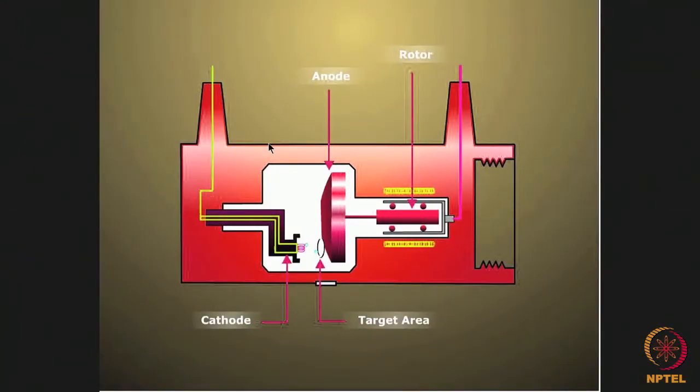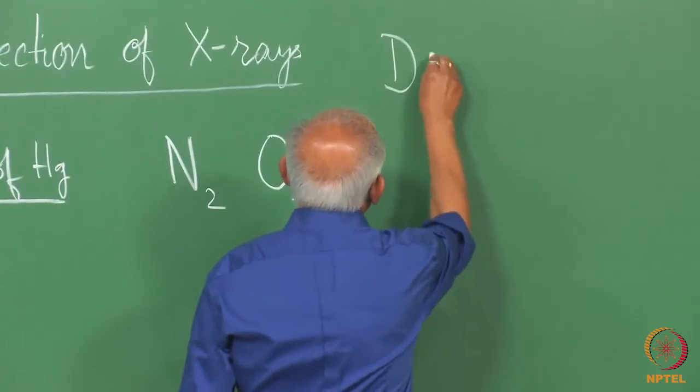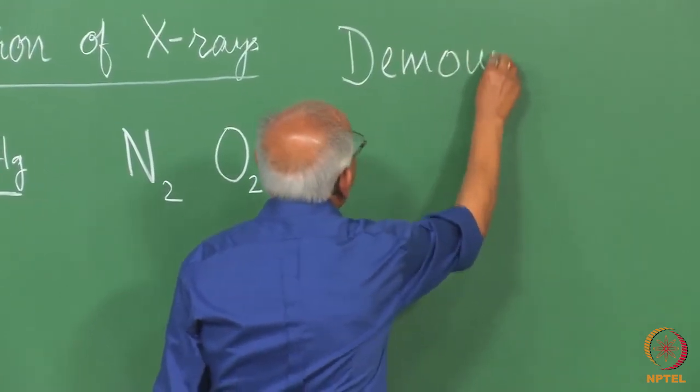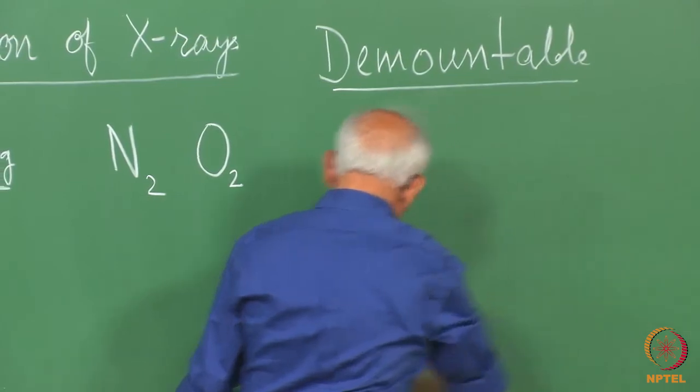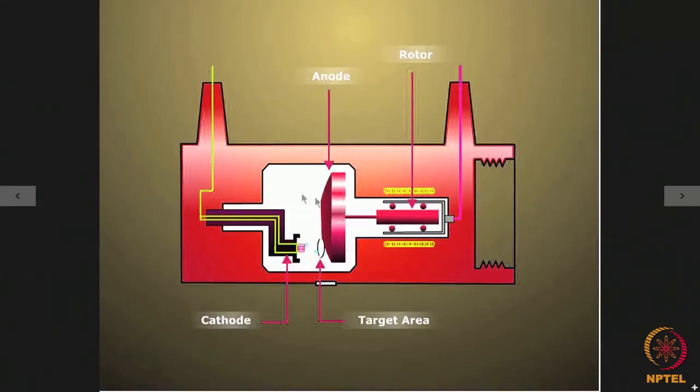There is a possibility that we have what is known as a demountable x-ray tube in which the target can be taken out and replaced by some other material. One disadvantage of this method is every time the target is taken out, the vacuum will be lost and again we have to evacuate it to a very high degree. Technically, it may not be that easy every time.